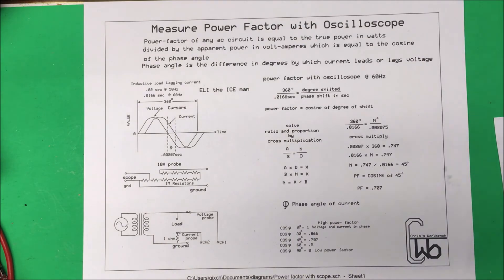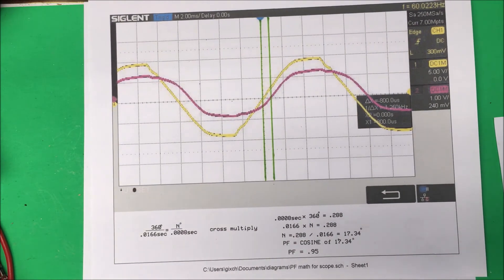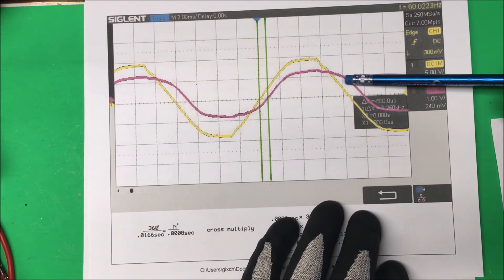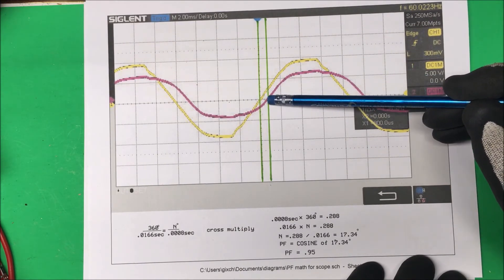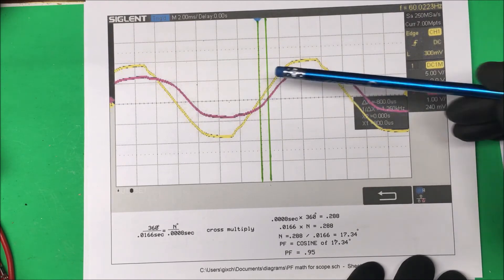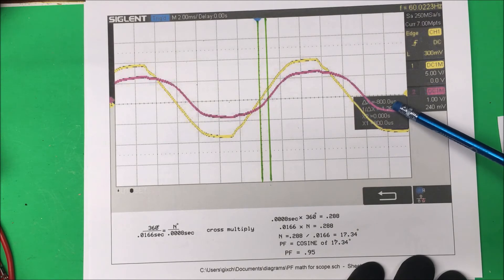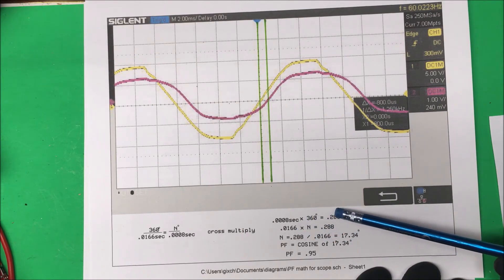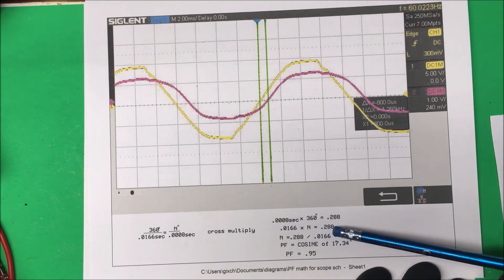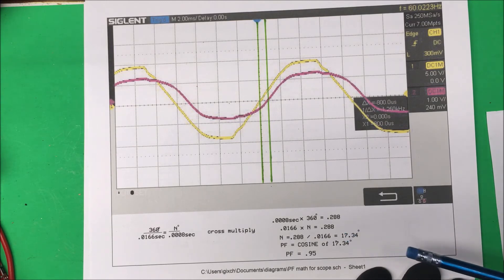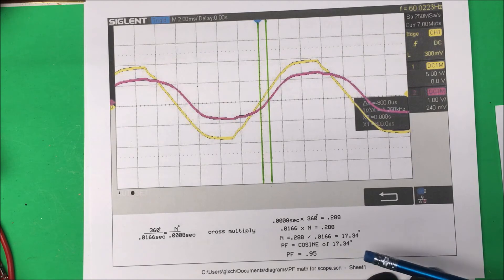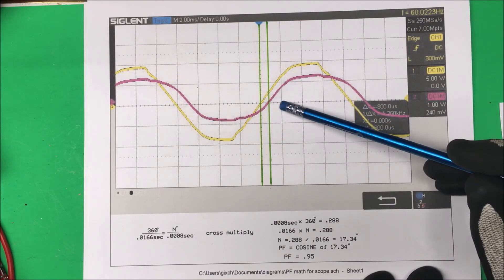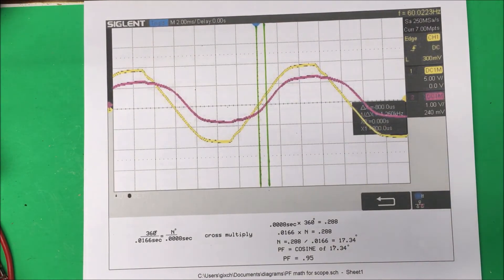Here's a real measurement — this is voltage and this is current. It happens to be an inductor, because voltage is leading the current. The zero crossing points are marked with two cursor lines, and the scope shows 800 microseconds between them. We multiply 800 microseconds by 360 degrees, get 0.288, divide by 0.0166 for 60 Hz, giving 17 degrees. The cosine of 17 degrees is 0.95 — a fairly good power factor for a lightly loaded bell transformer.